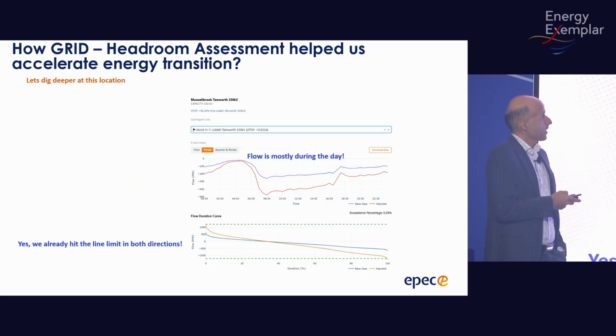From there, we look at the same line and look at the flow on this line. The blue line is N-0, the red line is N-1 for this line, Brook to Tamworth, for the trip of Lido to Tamworth. The flow is typically negative.